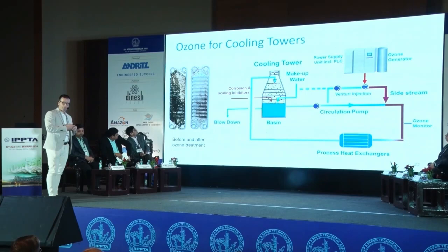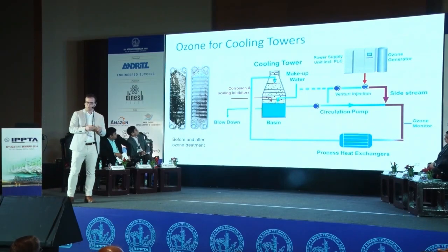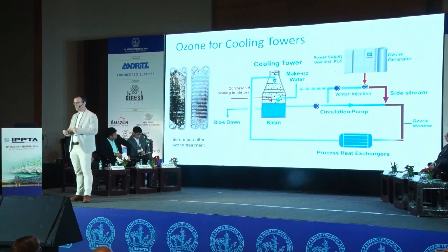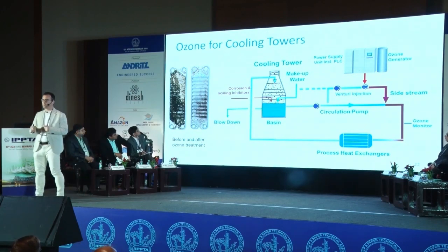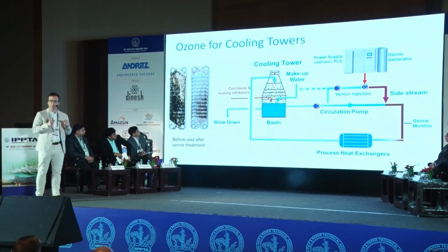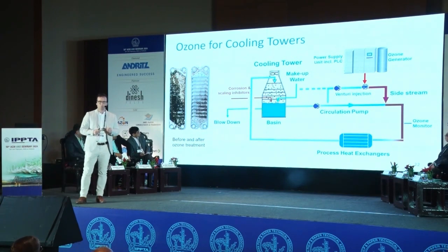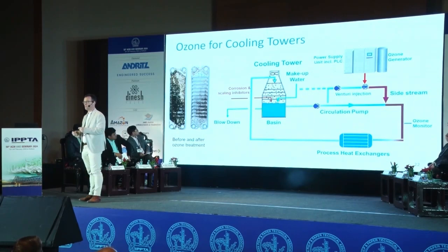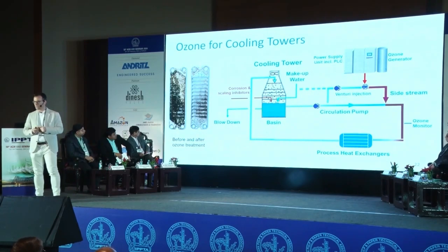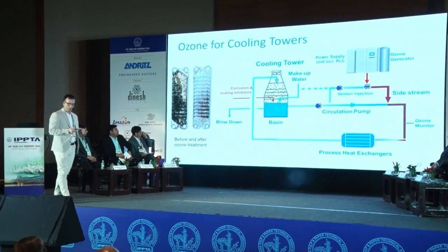Ozone can as well be used for treatment of cooling waters. Here, the ozone dose is extremely low. We need less than 0.3 gram per cubic meter. So it's below 1 rupee per cubic meter of cooling water treated. It allows not only to replace the biocide, but to reduce the amount of water purged from the cooling towers. So not only you don't discharge biocide into your effluent treatment plant, but you discharge less water as well.